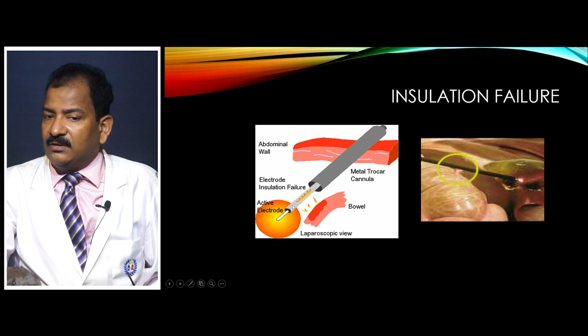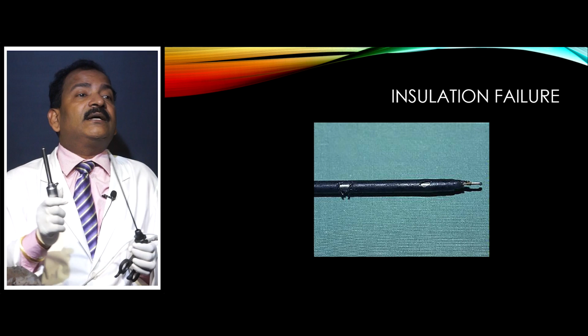This is a small insulation failure, this is a big one which you can see by naked eye, but sometimes the insulation failure is very small. Here in Lady Hardinge Medical College in 2007, 2 hernia surgeries were performed by a very good consultant. After 2 days, both came with perforation. An inquiry was set up. It was found that a new nurse had been appointed. She did not know how to clean the instrument. She saw a small clot of blood and scratched it with a knife. The next day the consultant came, did not see carefully, and used it. That is why Americans do not believe in reusable instruments. They always use disposable instruments.